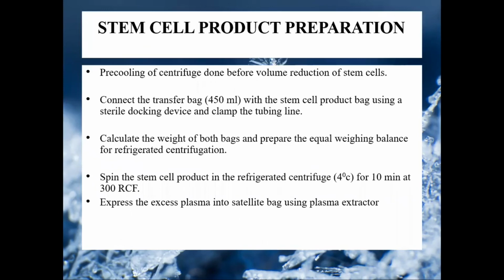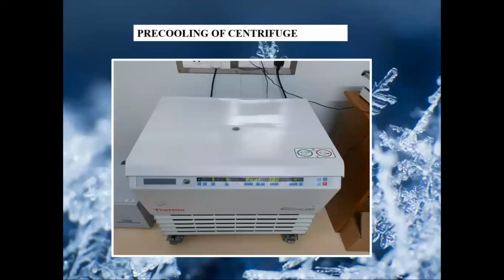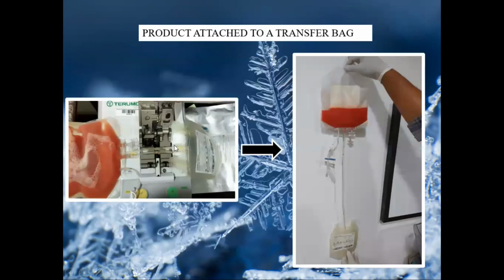So moving on to stem cell product preparation. First, I said there is volume reduction. Before that, I told you it can normally be kept at 2 to 8 degrees Celsius for 3 days. That was according to EBMT guidelines. So the stem cells are usually preserved at 2 to 8 degrees Celsius. For pre-cooling, the centrifuge has to be shifted to 4 degrees Celsius. For that, we do pre-cooling. After pre-cooling, the next step is volume reduction.